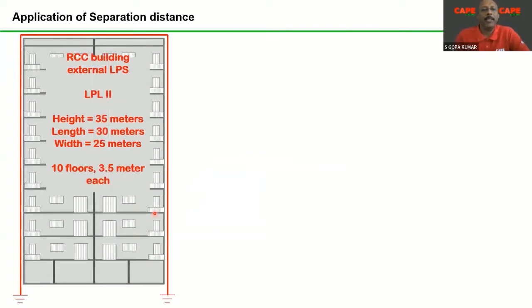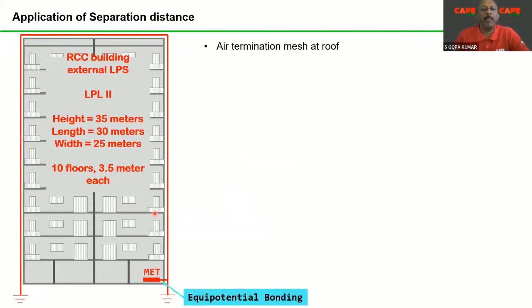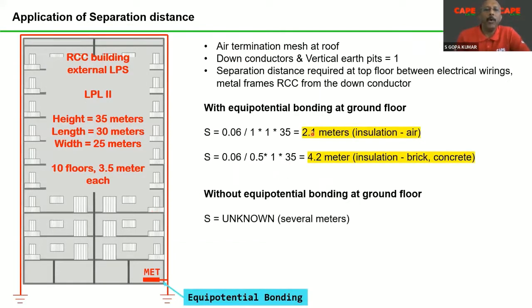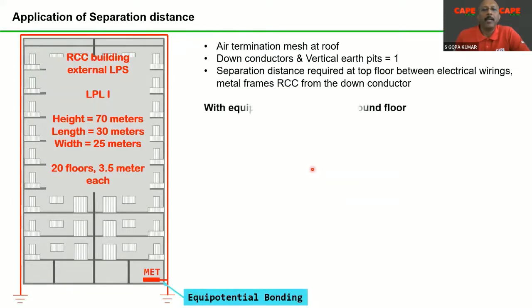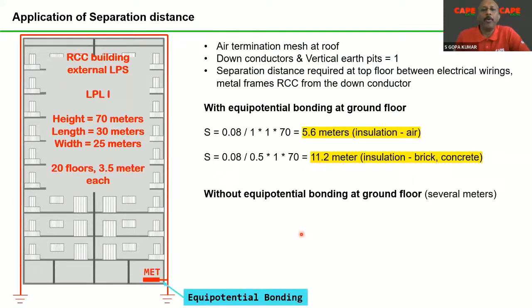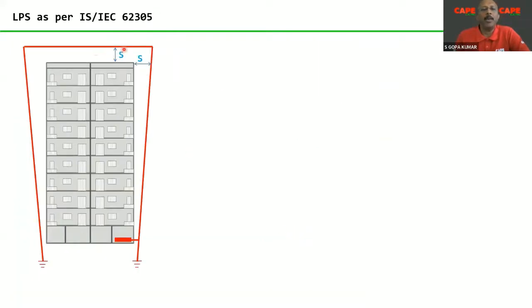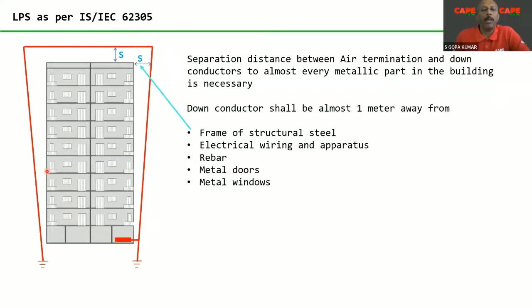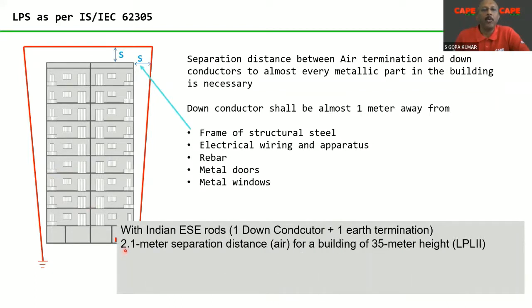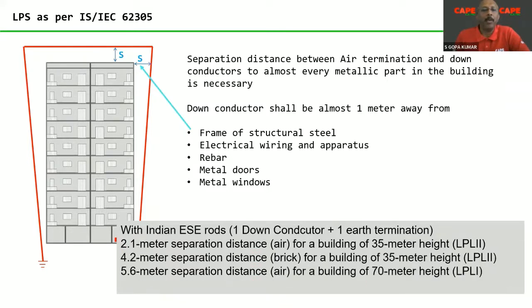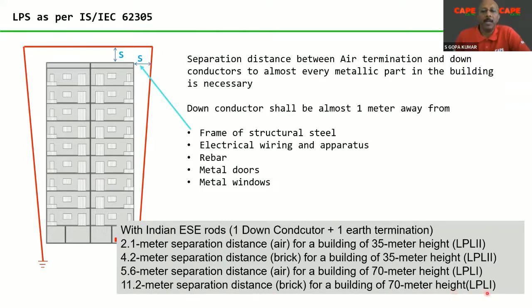If we apply the same separation distance for building number 1, a 35-meter building with equipotential bonding, you get a value of 2.1 meters. The separation distance required for an ESE rod is double the normal one. In brick, again 4.2 meters. For a 70-meter building, the calculation says about 5.6 meters, and 11.2 meters away from the building. What does it mean? It means the ESE rod and the down conductor have to keep the separation distance, in the typical Indian way, with one down conductor. In that case, the separation distance required is 2.1 meters for a 35-meter building with level 2, and almost 11.2 meters for a 70-meter-high building with LPL 1, where we consider the separating material is brick. So much distance away from the building.